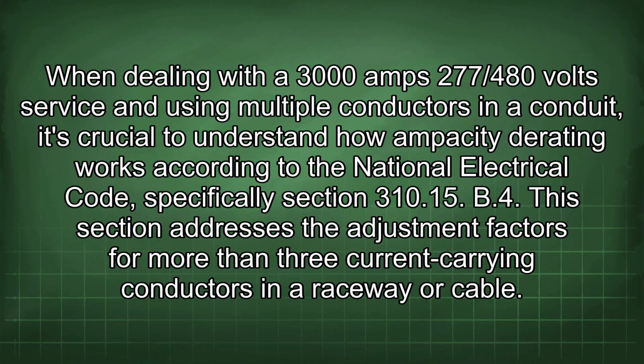When dealing with a 3000 amp 277/480 volt service and using multiple conductors in a conduit, it's crucial to understand how ampacity derating works according to the National Electrical Code, specifically section 310.15(B)(4). This section addresses the adjustment factors for more than 3 current carrying conductors in a raceway or cable.